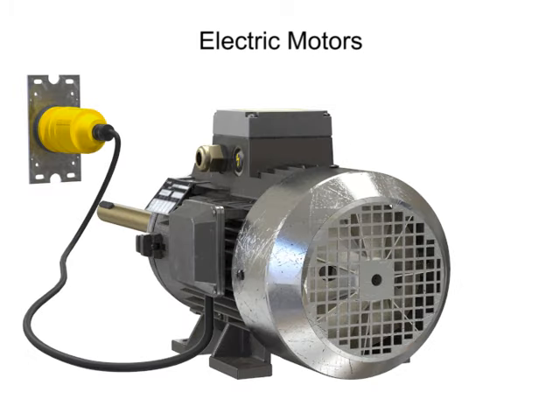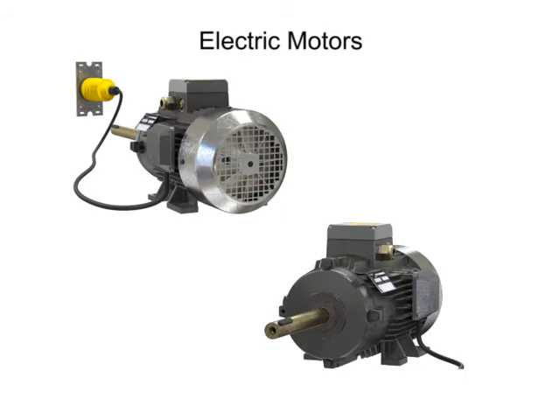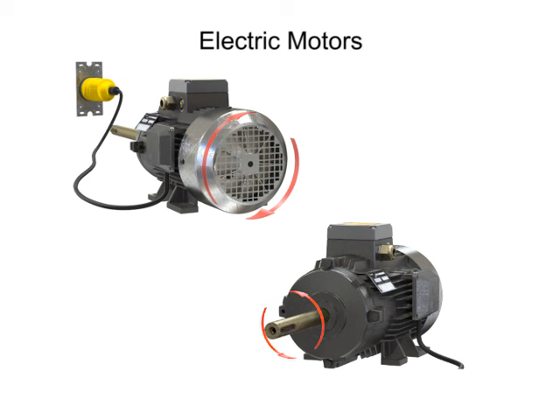While many motors are three-phase and easily reversible, others are not. For non-reversible motors, you must be very careful to check and double-check that the correct rotation is specified. Unfortunately, many vendors don't make it easy since the specifications of clockwise and counterclockwise depend upon the direction from which you view the motor.